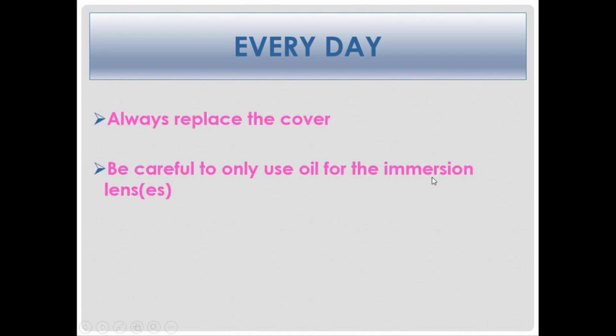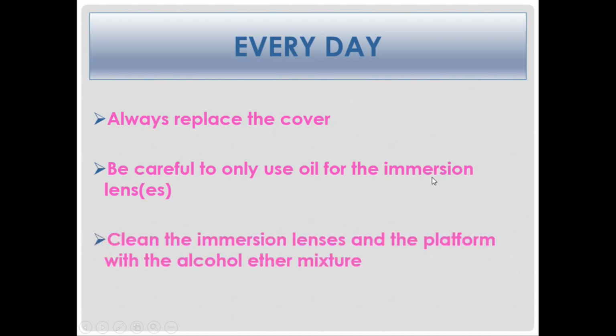Every day, systematically, you need to remember to replace the cover and to only use oil for the oil immersion lenses. Clean the immersion lenses every day to avoid a dry skin of oil encrusting on the lens, which will affect the clarity of your images. If you clean them every day with your alcohol mixture, they should never become clogged with oil.